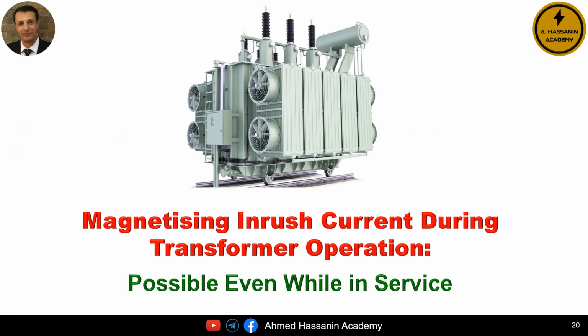At the beginning of the lecture, I asked a question. Is it possible for magnetizing inrush current to occur while the transformer is operating, energized, supplying loads, and in service? And of course, we said yes, it is indeed possible for magnetizing inrush current to occur while the transformer is in service, but how can this happen?